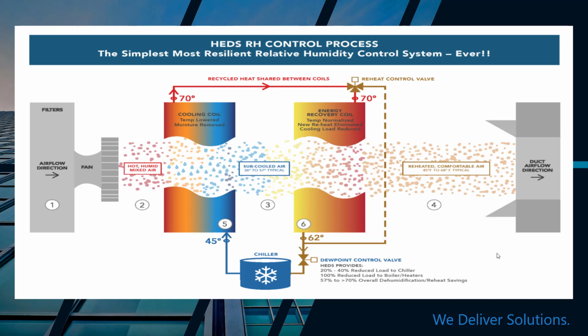HEDS is an emerging technology that we're excited about. It has relevance to the packaged chiller plant because of the variable set points that HEDS wants to implement on the chillers and on the condenser fans and the chill water pumps.